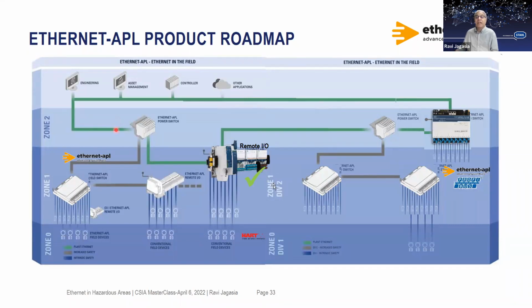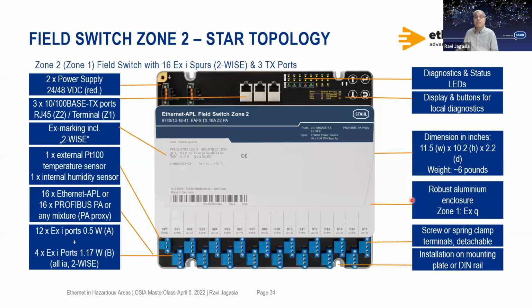And over a period of time or in a brownfield project, you can transition with a field bus power supply and the zone 1 or the div 1, div 2 field switches into the hazardous area. The field switch which we already have now is the one for zone 2. Coming up for zone 1 also, and specifically for div 2 for our market. Redundant power supply, 3 of the 100 base, 10 base TX ports with RJ45 in zone 2, intrinsically safe terminals for zone 1. This is the marking label which you can see.